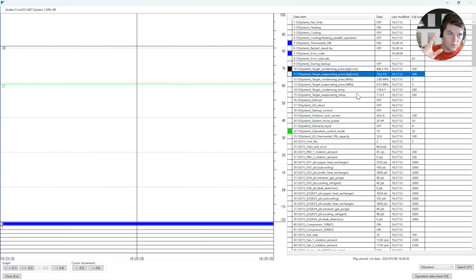Whichever one it's driving to in that system, or I can go and look at the spread on the indoor unit demand for those in heating and in cooling and kind of determine, hey, if I've got 16 indoor units and we have 10 that are calling for heat and we have 4 calling for cooling, it's obviously going to be controlling off of target condensing pressure. I plot that on the graph and I look at that in that timestamp to find out what is it doing and why. Okay, that's heating, cooling, parallel operation. I'm giving that one to you for free, like everything else that I'm doing here for that little tiny nugget. That's not what we're here to talk about.